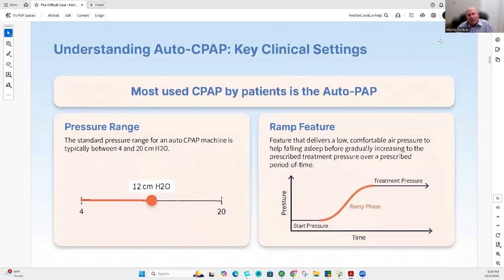The ramp feature on all CPAPs, you'll have kind of like a little plate that has power, and to the side, you have somewhat of a button. What a ramp does is it'll drop the pressure. So if your pressure started at 8 and the patient's going, my brains are being blown out, it's too strong, you hit the button and it'll drop it down to, say, 4, which is a very light amount of air coming in. And then you set the ramp at a time frame. I found 15 minutes to be adequate, so that during the first 15 minutes trying to get to sleep, that pressure is going to gradually increase to what your initial settings were. So that's the ramp feature.